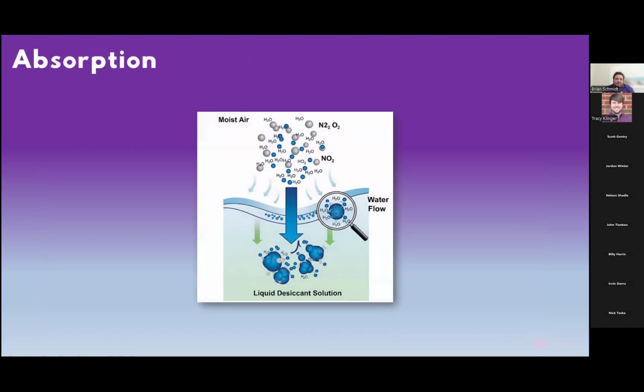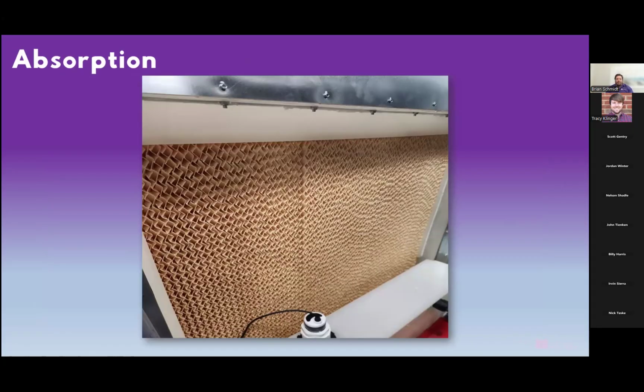All right, so switching gears a little bit, as I mentioned before, what we are doing is absorbing moisture from the environment, right? So we have water in the air, and we are absorbing it into the liquid desiccant itself. How do we do that? Well, we have a pad. So this is the absorber pad. The desorber pad is very similar, a little bit bigger. But essentially, concentrated liquid desiccant flows through a header at the top of this pad. It is then permeating or penetrating this pad.